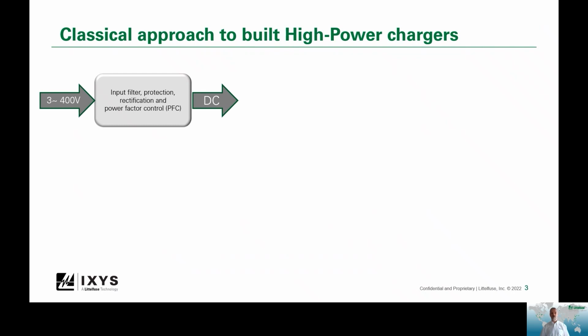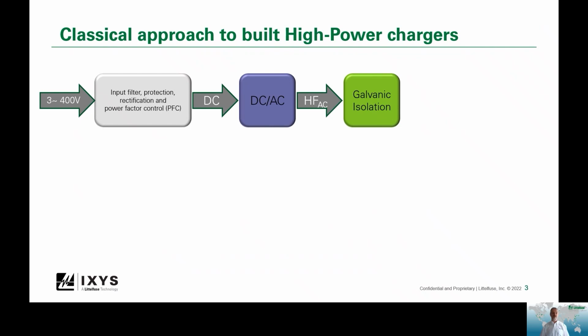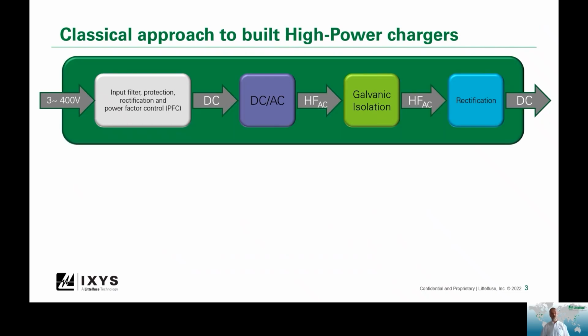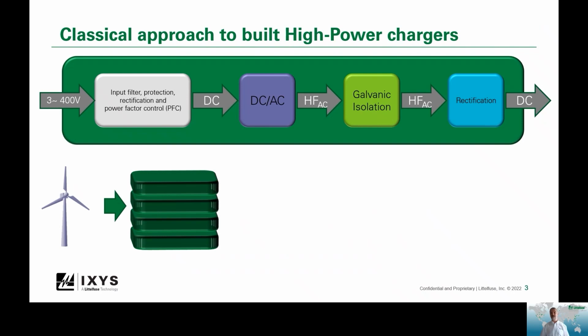So classical approaches to build this are based on a three-phase supply, typically 400 volts in Europe, which is rectified. Then the DC link is converted into a high-frequency AC. The high frequency is needed to drive an isolating transformer, so the galvanic isolation becomes part of the scheme. Then the high-frequency AC is rectified and given to a battery in the form of DC. All this is packed into one power module or subunit, forming something like a 60, potentially 80 or 100 kilowatt subsystem, which is used to charge the vehicle, and the sum of those subsystems is stacked and then provides high power levels to a single battery.